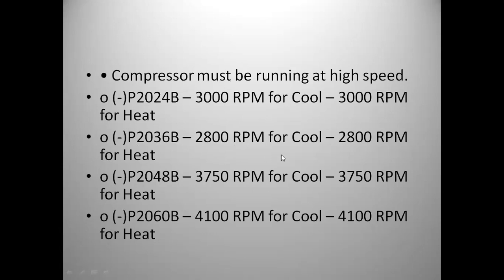RP2036B, 2,800 for cooling, 2,800 for heating. And you can verify your RPM speeds, inverter RPMs, from the EcoNet. So you'll get an idea that, yes, I indeed am running about where I need to be. RP2048, you should be upwards around 3,750 on both cool and heat. And then RP2060, you should be somewhere in the range of 4,100 RPMs for both cooling and heat. So if you're approaching those RPMs, then you know you're in a stable high stage speed. And at that point, the unit just needs to run and stabilize.